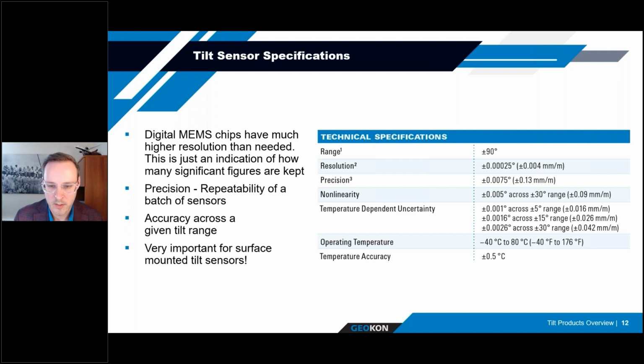So we've specified this parameter across 3 different ranges. The closer to vertical the sensor is installed, the better the temperature dependent uncertainty. Every manufacturer would typically do their own temperature correction and would have different algorithms and proprietary ways of correcting that. And for our calibration process, we've decided to present the specification in 3 different ranges. And then of course you have operating temperature and the accuracy of the temperature sensor itself.